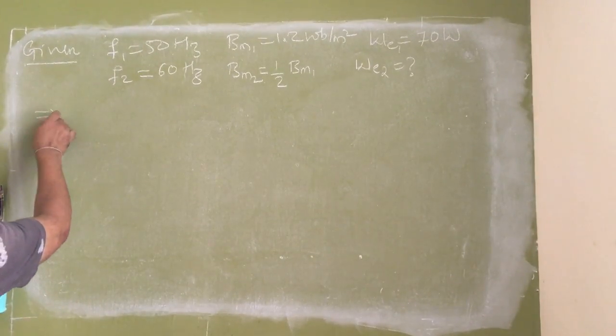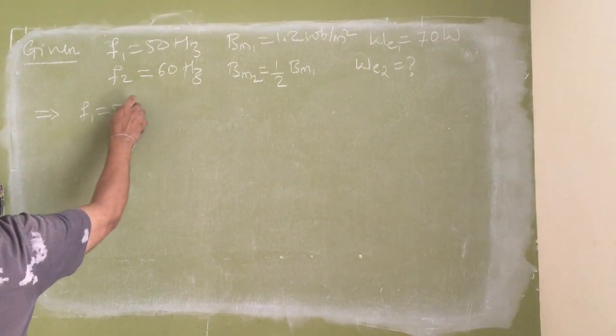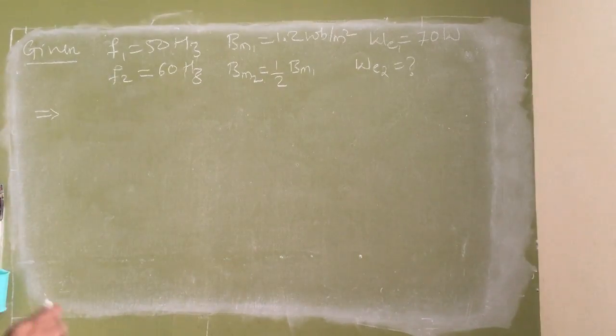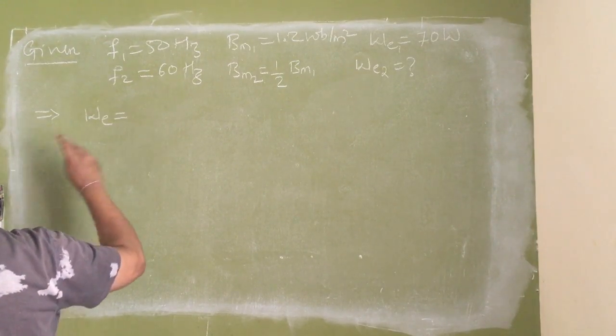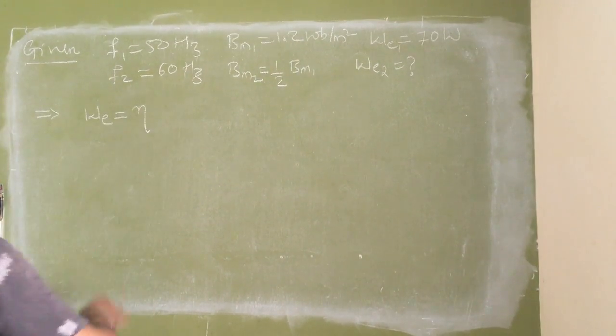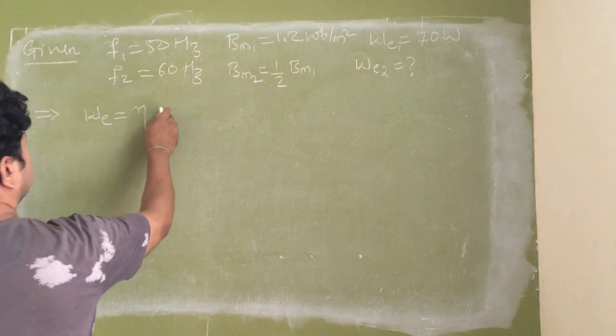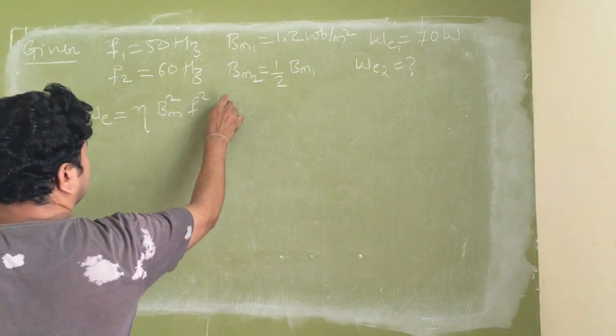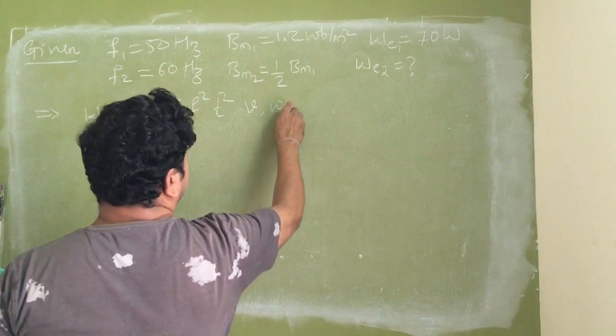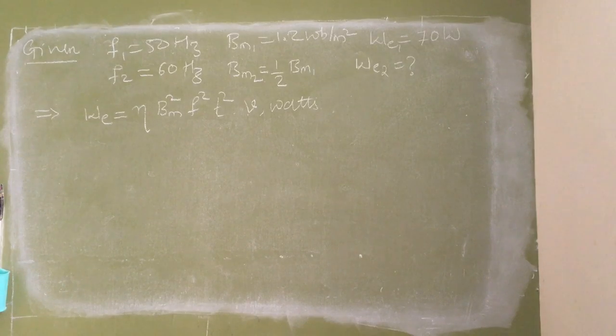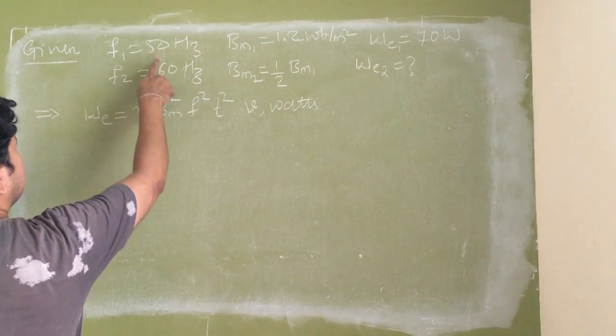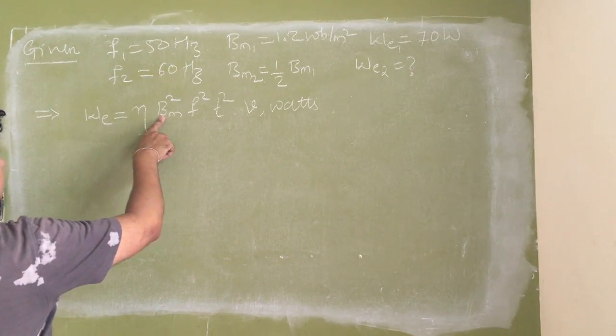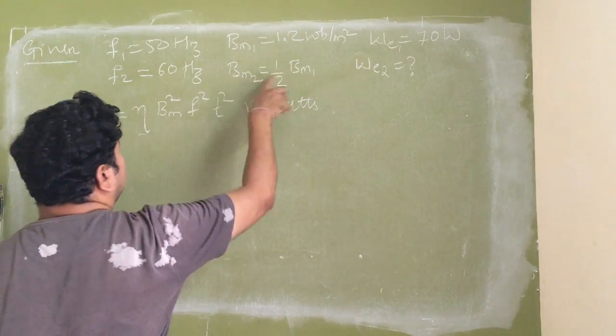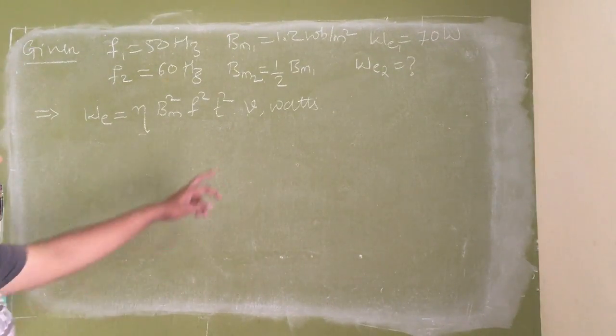So, solution for F1 equals 50 Hertz, or generally we will see first. Eddy current losses are given as WE equals some material constant. You can take eta, beta, zeta, K1, K2, whatever. It is a material constant. Okay. Bm square F square T square into V watts. Now, the material constant is constant for the type of material I use, it won't change. Frequency is once 50 Hertz, once 60 Hertz, so it is changing. Maximum flux density is once 1.2 Weber per meter square, second it is half of that value, so it is changing. Thickness of core is constant, volume of core is constant.